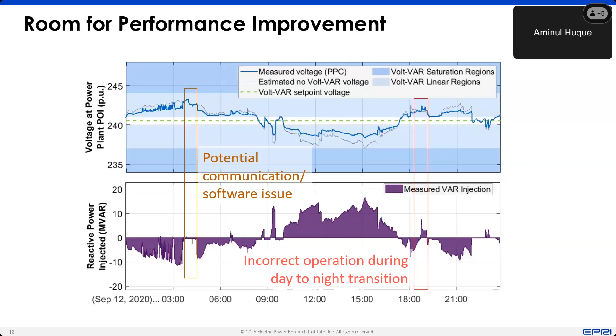We have also seen some issues when the plant goes from daytime to nighttime, basically during sunset, when it has a switchover mode of control. Again, these are manufacturers' proprietary things. They did not disclose all the details, but there are some challenges in keeping the transition seamless. Again, this is because this project was not targeted for this application from the get-go. But as we showed with the other inverter testing we have done in the lab, it can be seamless. So one thing I wanted to highlight is that if this is in the scope, then it should be thought through properly, working with the manufacturer and the contractor to configure the system correctly so that it can operate the way we want it to operate.